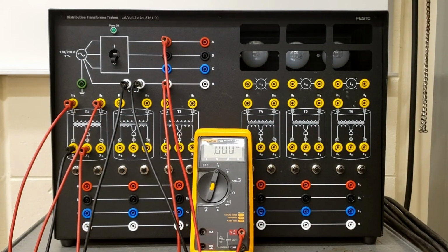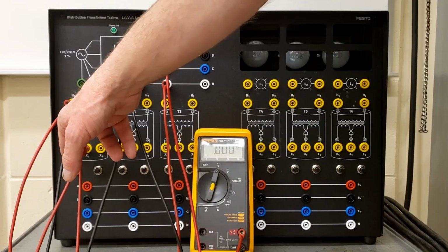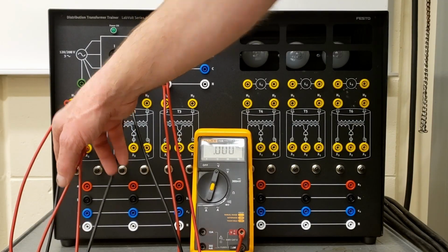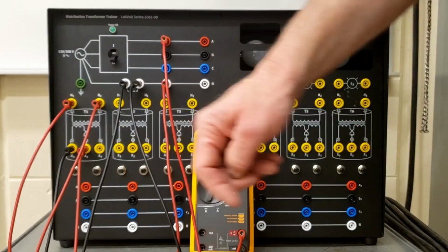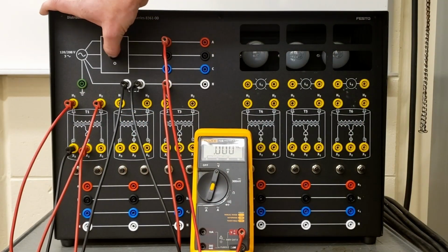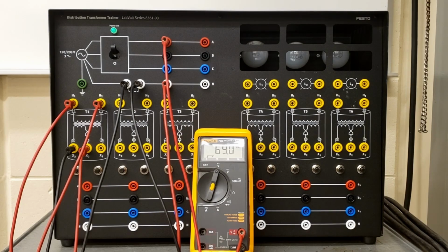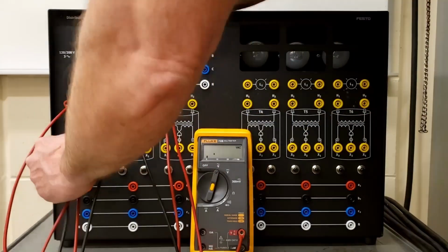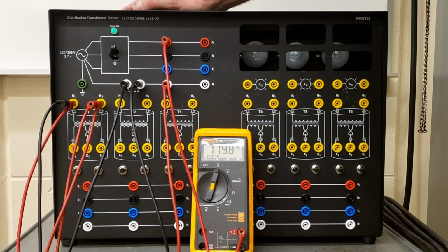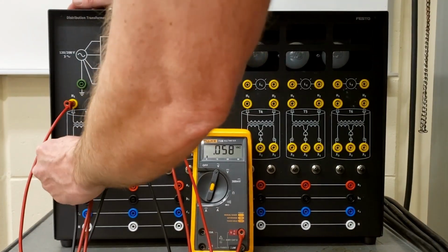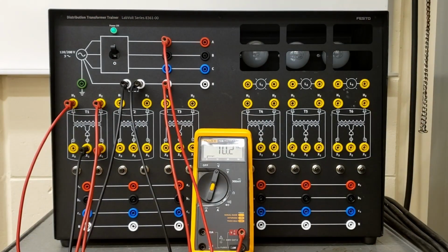Okay, and then we said that if it's root 3 less, if we have 120 volts here, then we're going to have 1.732 less on the secondary side. So we should have 120 volts on the primary, and then we should have 69 or 70 volts on the secondary there. Beautiful, 69. Excellent, okay? And if we look there, obviously the voltage is 120 on the primary. So 120 on the primary. The ratio still stays the same, so that's primarily what we're looking for, the discussion of the ratio of the windings. If you put a lower voltage to the primary, then obviously you're going to get a lower voltage on the secondary. That takes care of page 5.